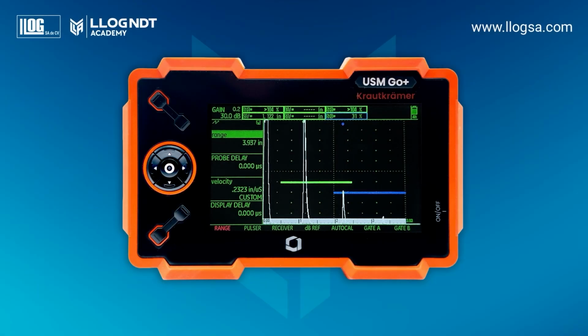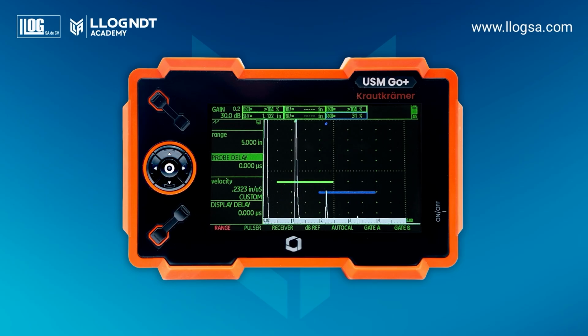Now we will perform the preliminary adjustments for standardization using a dual crystal probe. Set the range to 5 inches. Set the probe delay to 0 microseconds. Select the velocity for longitudinal waves in steel. Display delay 0. Set the voltage and energy to high. Damping 50 ohms. Pulse repetition frequency auto high.